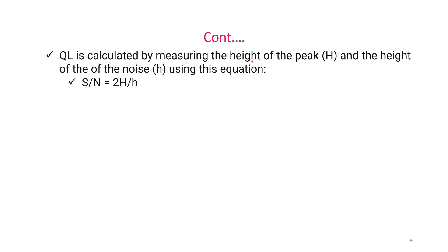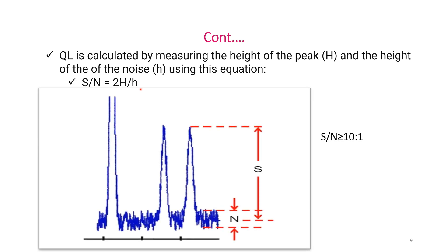QL is calculated by measuring the height of the peak (capital H) and the height of the noise (small h) using this equation: S/N = 2 × H ÷ h — the same as discussed for detection limit. S/N should be greater than or equal to 10:1. Capital H is the height of the signal, small h is the height of the noise, and using this formula, S/N and QL are calculated.